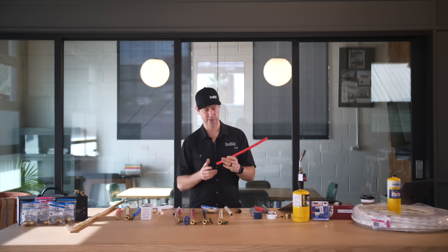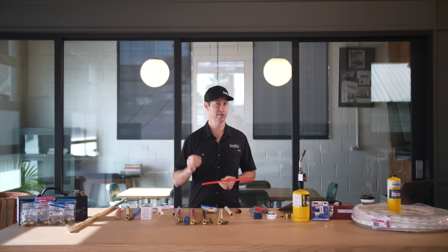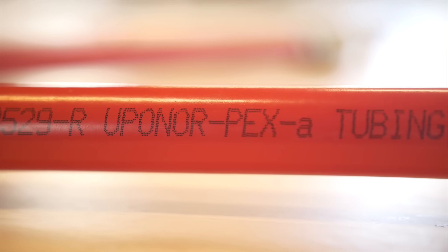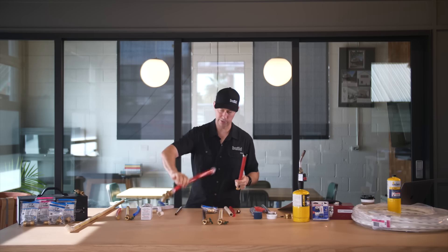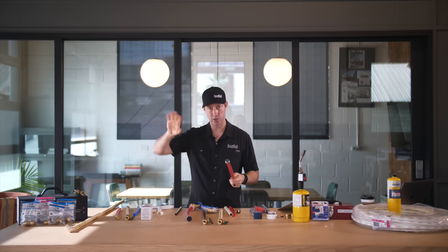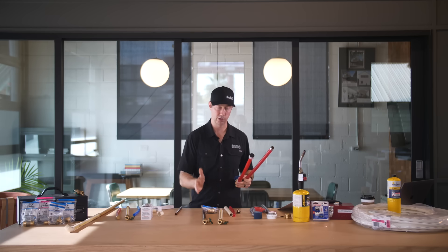Rounding out the bunch is PEX. I've used PEX the most in my houses over the last 15 years. There are three varieties — PEX A, B, and C — that's not a grade, just a manufacturing process. The two most common in the marketplace are PEX A, such as Uponor PEX, and PEX B, such as Viega PEX, which I've used a lot. PEX A is a little more flexible and easier to move around in the wall system; PEX B is a little stiffer, though still a flexible pipe. You can go much longer before needing a fitting with PEX compared to either copper or CPVC.